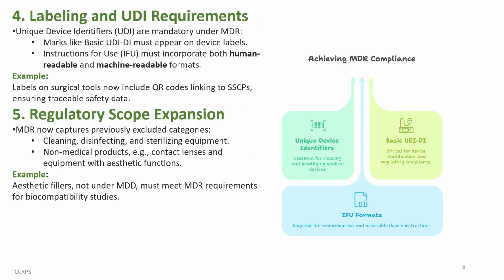Labeling and UDI requirements. Unique device identifiers, UDI, are mandatory under MDR. Marks like the Basic UDI-DI must appear on device labels. Instructions for use must incorporate both human-readable and machine-readable formats. Labels on surgical tools now include QR codes linking to SSCPs, ensuring traceable safety data.